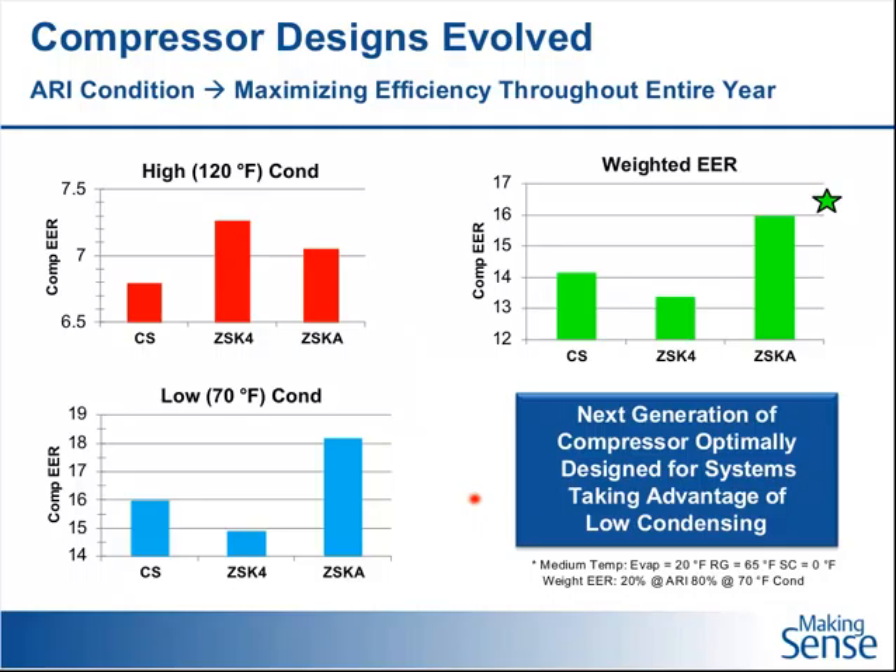The hermetic compressor is stopped at a 70-degree ambient because the minimum condensing temperature currently approved is only down to 70 degrees condensing, which corresponds to a 50-degree ambient temperature. The majority of systems today have a minimum of 90-degree condensing, and with the 20-degree temperature differential, that would equate to a 70-degree ambient. You can see you're benefiting from lowering your ambient temperatures from the 100-degree range down to the 70-degree range. But at that efficiency level, you're capping the efficiency of your equipment, and for the majority of the rest of the year you're maintaining at that energy efficiency level or EER. You're actually wasting the energy performance increase you can gain by allowing your systems to float down to those lower condensing temperatures.